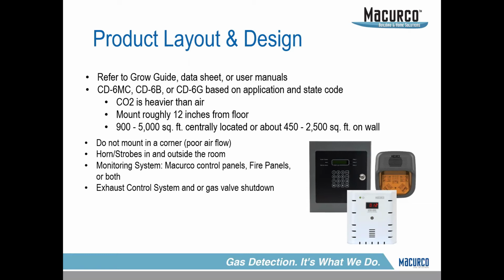Most of our products, again, have a square foot coverage range. We base it on airflow, we base it on where you're mounting it. So if you're mounting it to a wall, your square footage gets cut in half. If you're mounting it in a pillar or a column of a room, you'll get that full coverage. Is there a science behind it? I mean, technically, if you look at a sensor, the sensor's covering about 1.25 inches. But with all the legislation on airflow and air movements, all of our competitors and us, they all follow that same connotation. So that's kind of how we go about that portion of it.